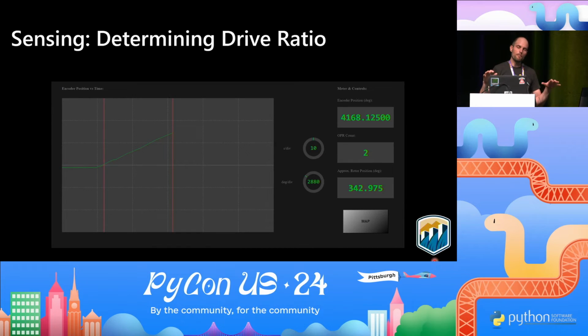So I call this mapping, and the reason I call it mapping is because if I know the pole count of the rotor, I can now make a map and say, for example, just making up numbers, click 473 of the encoder needs to be forward on green phase to get clockwise rotation. I can build that map now, and store it in a database for later recall on that particular machine in the asset.